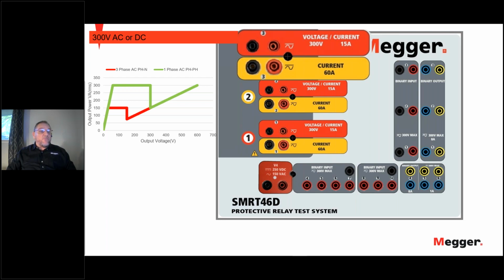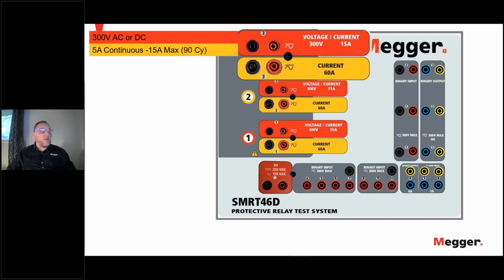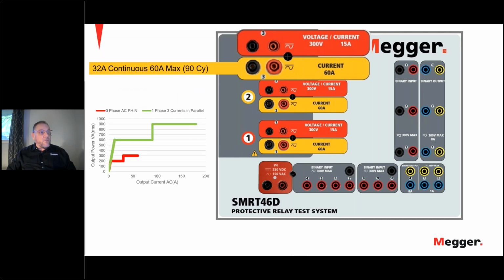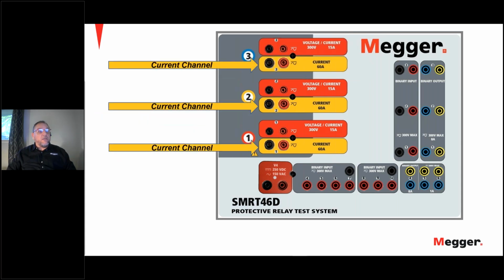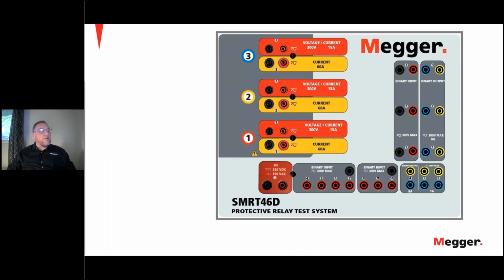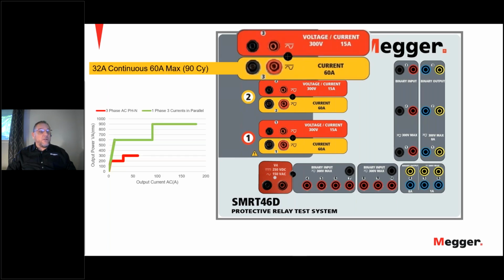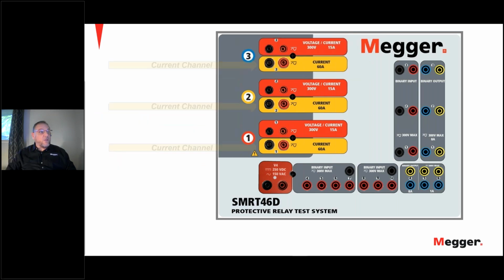The voltage channels can be configured and used as current channels with, again, 5 amps continuous or 15 amps for 1.5 seconds. The yellow channels are current only, and the channels have a maximum of 32 amps. Sorry, I missed something there. So 32 amps and an absolute maximum output of 60 amps. And again, by putting these units in series, you can definitely achieve a higher output capability of these channels. Okay, moving on.